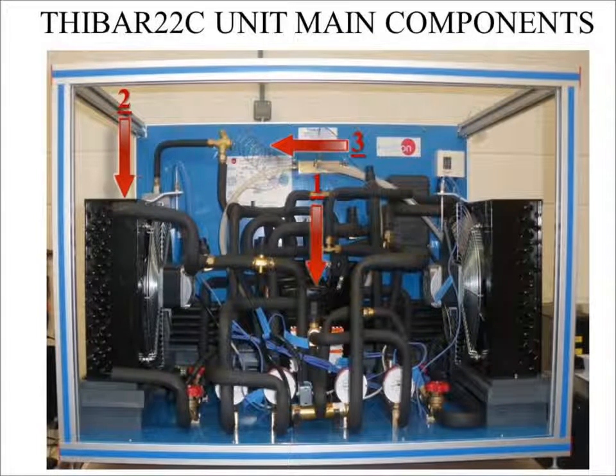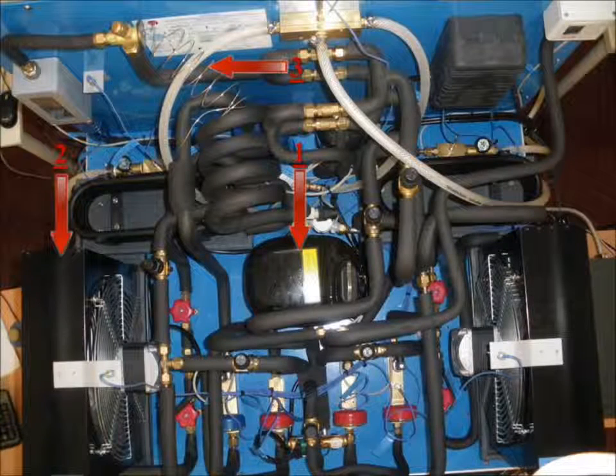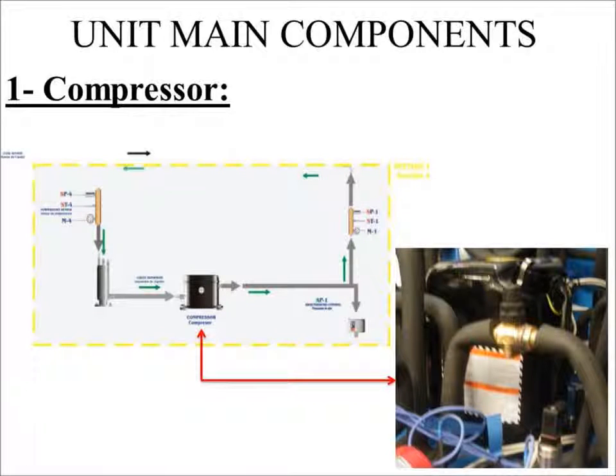THIBAR22C unit main components. Number 1, compressor. Number 2, condenser. Number 3, expansion valve. There is a top view of the unit for a better visualization. Unit main components in detail. Compressor. The compressor is a device used to increase the steam pressure until it reaches the condenser's pressure. This pressure increment increases the temperature at its outlet.